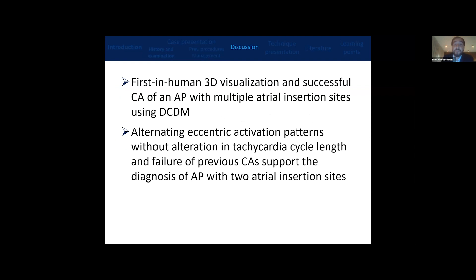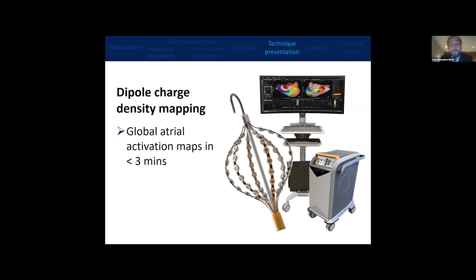charge density mapping. This is a novel high-resolution non-contact mapping system which offers superior spatial and temporal resolution and allows the diagnosis of complex arrhythmias based on a single beat. The system is based on a basket catheter, the AcQMap, and its console, the Acutus system. This basket is composed of 6 braces. On each of them, you can see 8 ultrasound transducer electrodes, and between them, the biopotential electrodes. All these permit us to assess global atrial activation maps in less than 3 minutes.